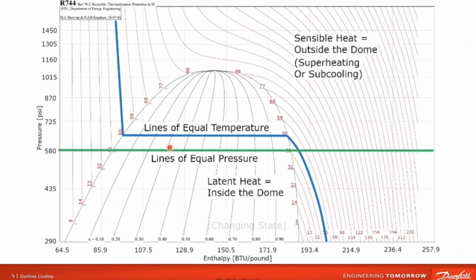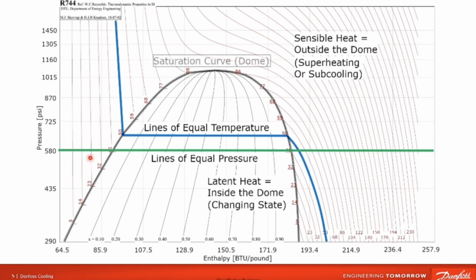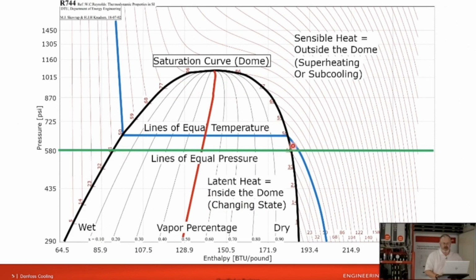So outside the dome here, let me highlight the dome for you. Outside the dome, you have sensible heat that you can measure with a thermometer. Inside the dome, you have latent heat that doesn't change the actual temperature. It changes the state of the refrigerant. And inside the dome, by the way, is where we do 90% of our work. We do superheating and subcooling for other reasons, but the majority of heat transfer happens inside this dome.